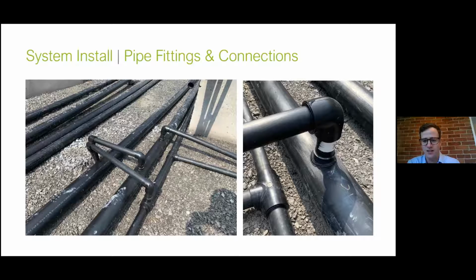We also had saddle welds. In the photo on the right, you can see one of the branch lines connecting to the main run - that has to be a field connection. There's no real efficient way of prefabricating that offsite. So there's a nipple that's actually heat welded onto the main pipe, then the hole is drilled out after, and the final connection for the branch piping is made.